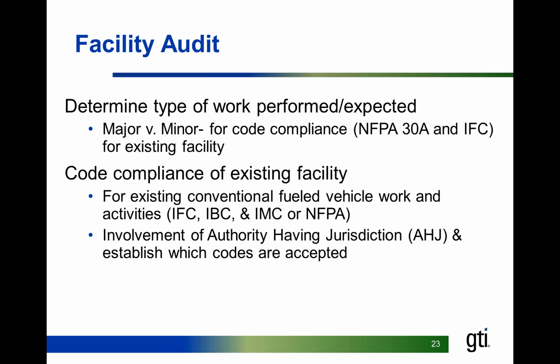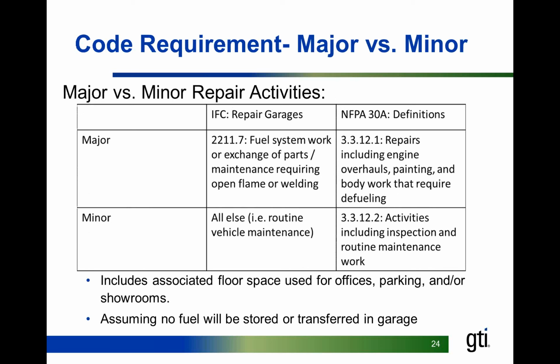So if you have propane in your facility, it's similar. The facility audit stage is very similar. You want to determine if you have major or minor repairs being done. Clearly, you have to involve your local authority. You have to determine what your key codes are and what they will be approving your facility on. The major difference with propane versus natural gas is that mostly if your facility meets traditional fuel, gasoline and diesel fuel maintenance codes and standards, it will mostly meet it for propane as well, because the fuel is similar and the hazards are similar.